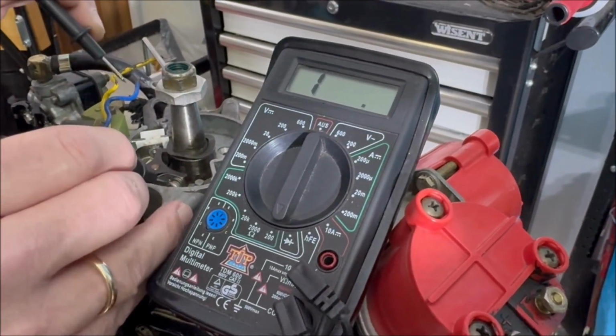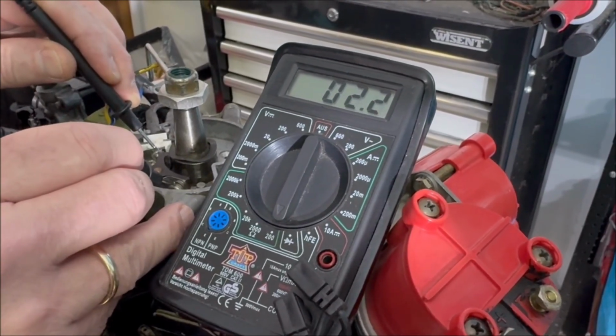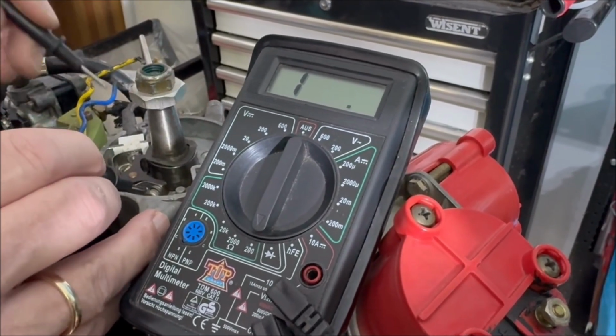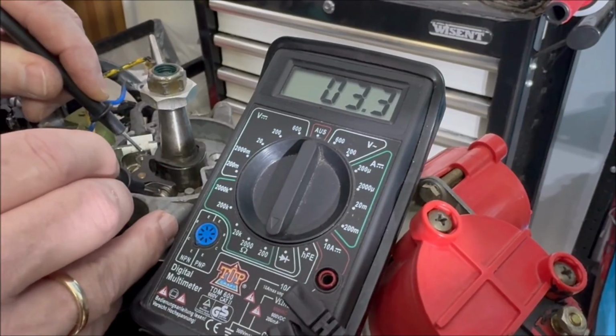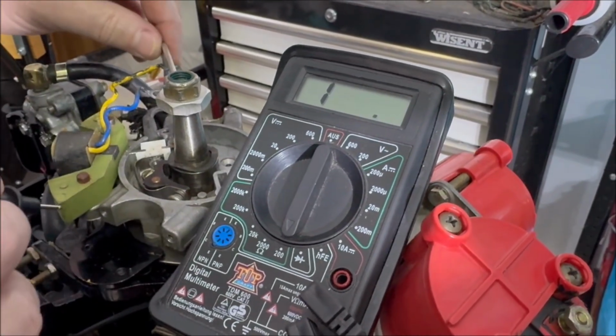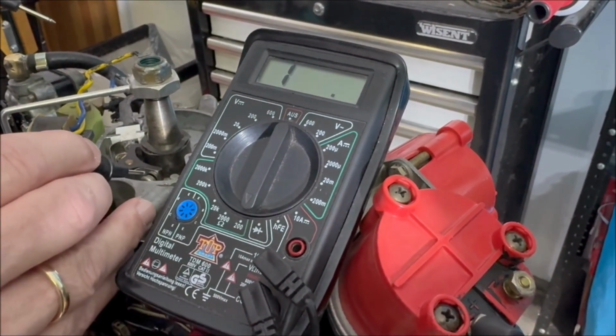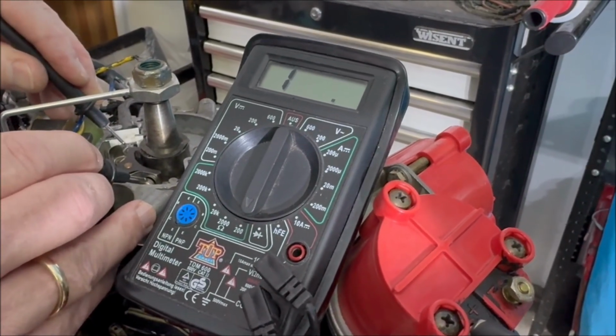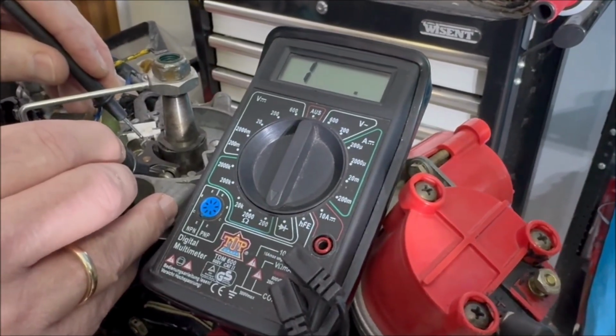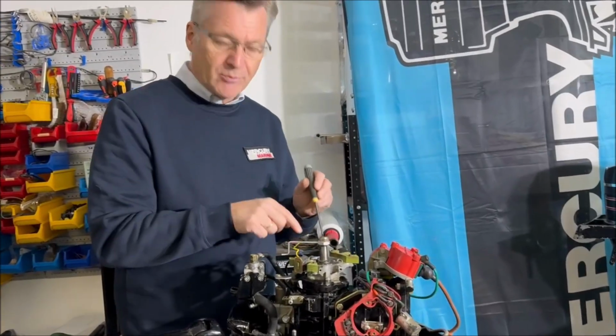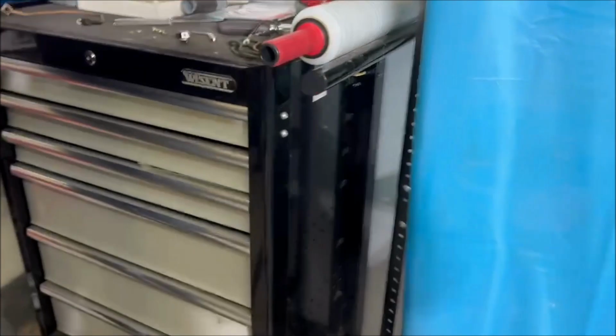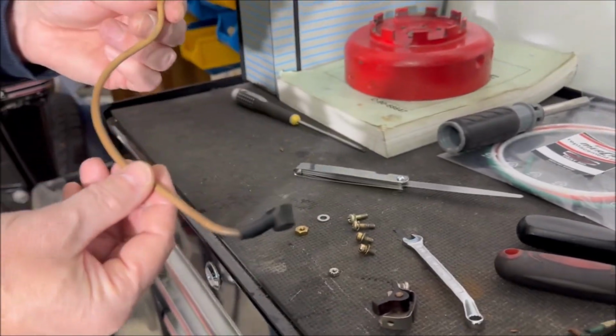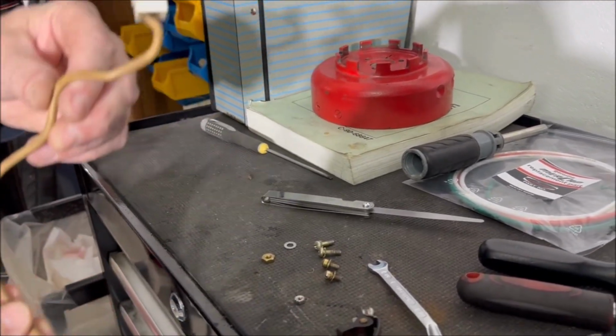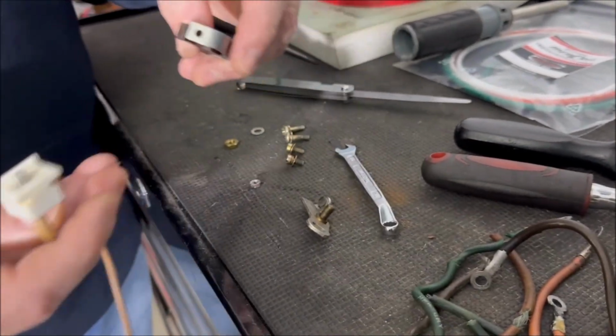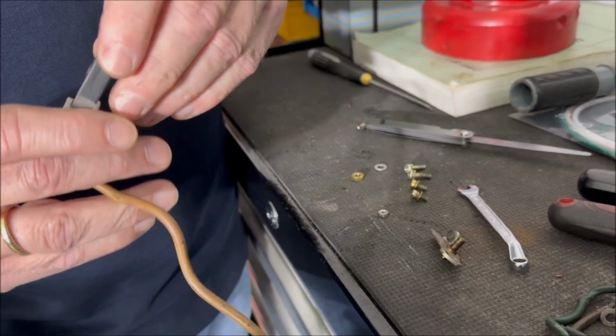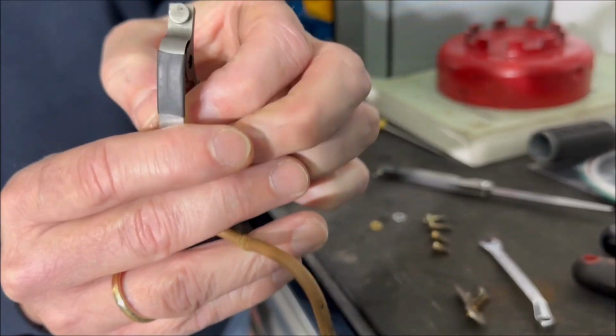So we're going to measure the resistance to see that the breaker actually works. So now it's closed. So that has a very low resistance, which looks good. So let's see that. Yeah, that's okay. And now we're going to open the point and we're going to measure again, and we can see there's no connection. And that's exactly what we need. So now we're going to install the other point over here. So for that, we have checked the cable, and the original cable actually looks quite okay. So it doesn't have any cracks. And what we're going to do is we're going to take the point, put it on, and tighten the screw.